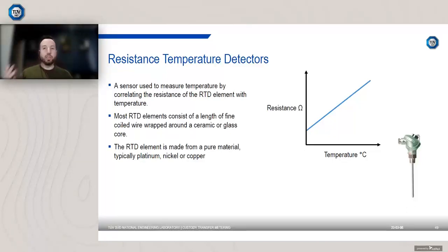They also come in different types. So you've got PT100 RTDs. That just basically means if you measure 100 ohms, that it should be at a temperature of 0 degrees Celsius. But you also get PT25 and PT1000 are another sort of common type of RTD.